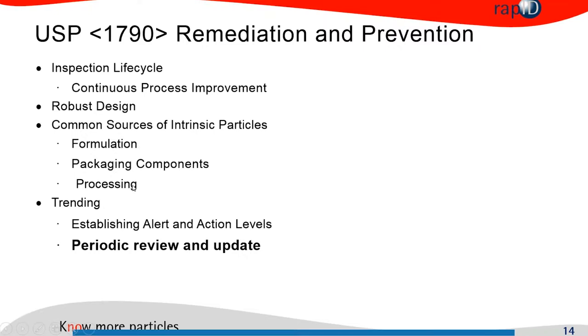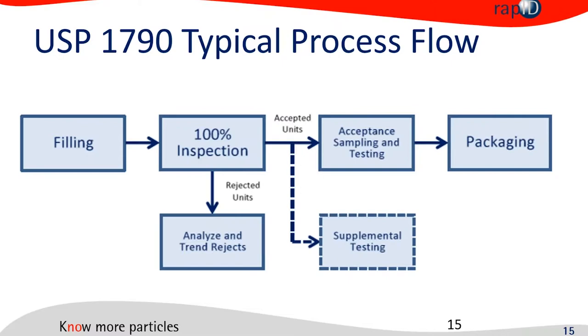Common sources of intrinsic particles include the formulation and packaging components. The long-term goal is to establish alert and action levels, which you can only do properly with periodic review and update. The typical process flow for the 1790 is that after filling you do 100% inspection, and what we are talking about today — analyzing and trending rejects — happens after that 100% inspection step.